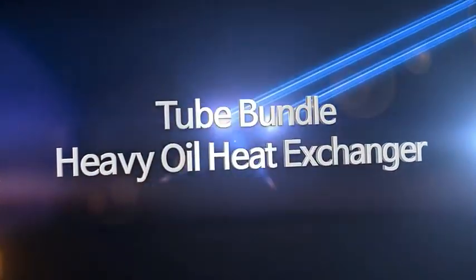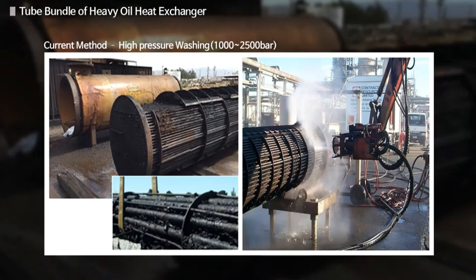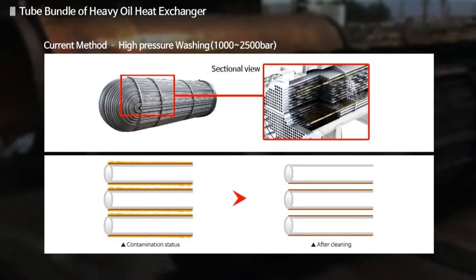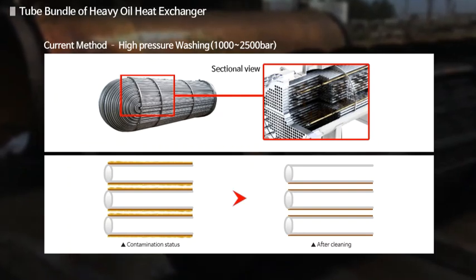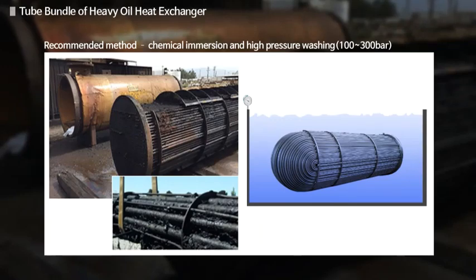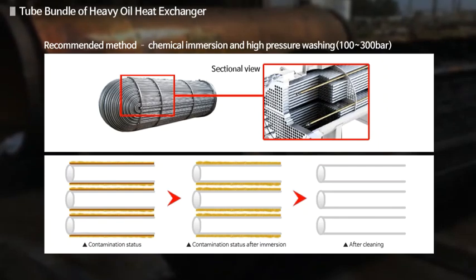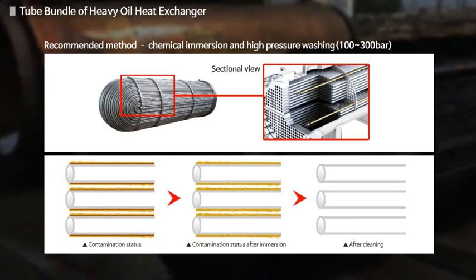The fifth is the tube bundle of an oil heat exchanger. The current method is high pressure washing with 1 to 2.5 kilobar of water, which has the problem that only the outermost part of the bundle is cleaned while the inner part is hardly cleaned. On the other hand, our method uses chemical to weaken the hard scale like soft scale and then wash it, which can remove scale in the inner part of the tube bundle as well. Please watch the video to learn how.